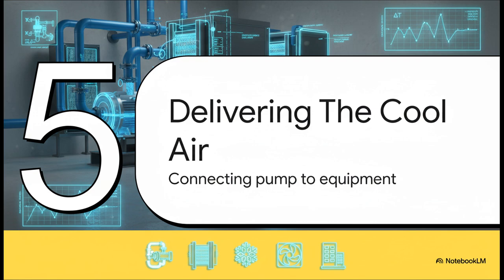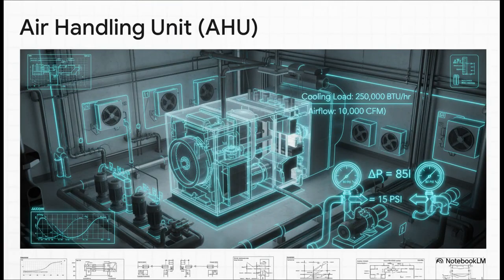This is where all that hard work pays off. The main workhorse for cooling in a big space is usually an air handling unit, or AHU. It's basically just a big box that uses our chilled water to cool down a massive amount of air. But here's the key thing to see. It's how it all connects. Remember that coil pressure drop we used in our calculation? We had to get that number from the AHU manufacturer before we could even size our pump. Every single component in the system depends on the others.